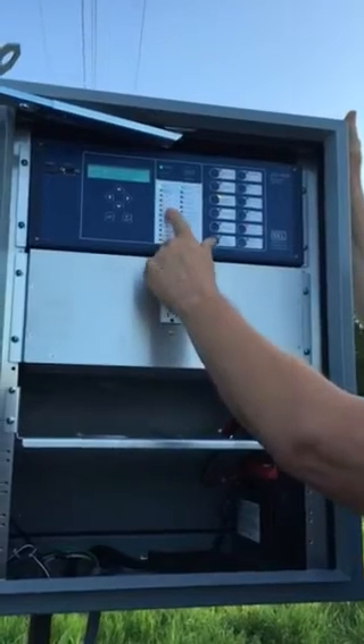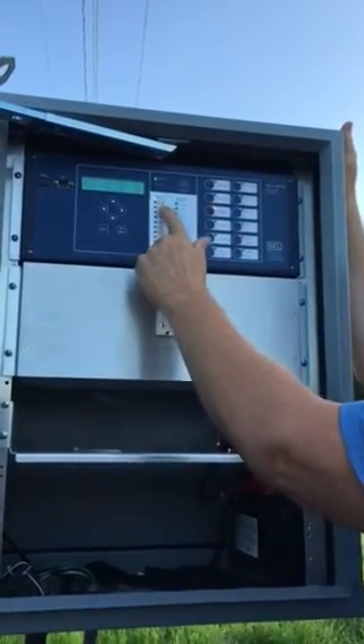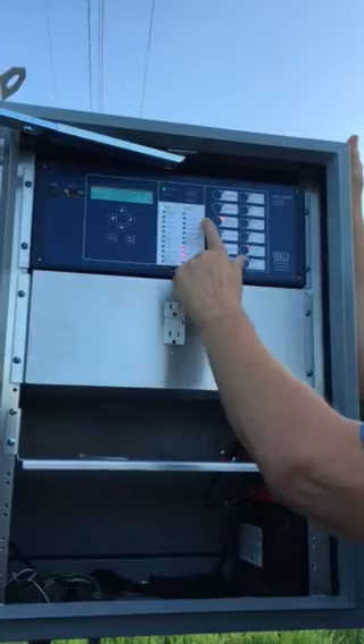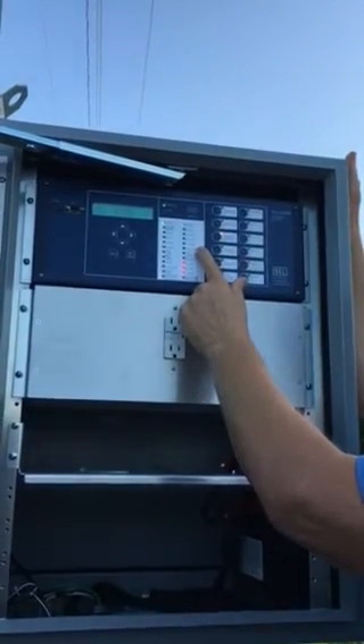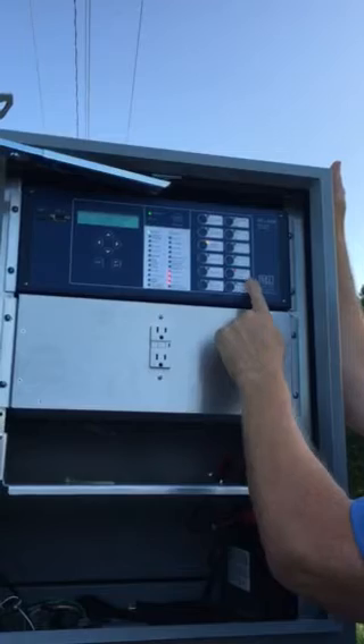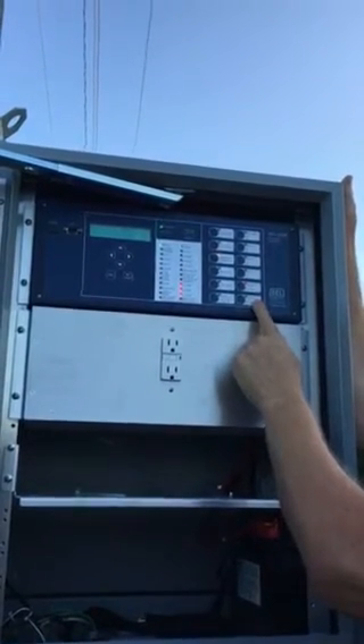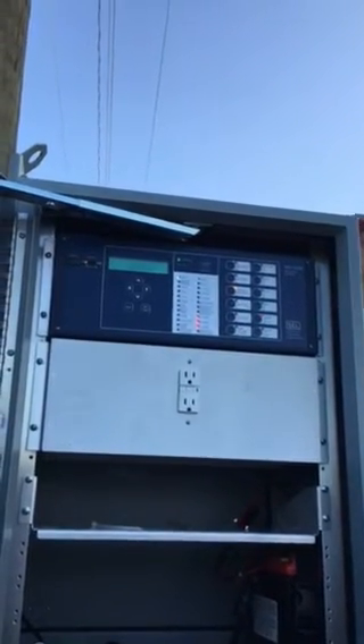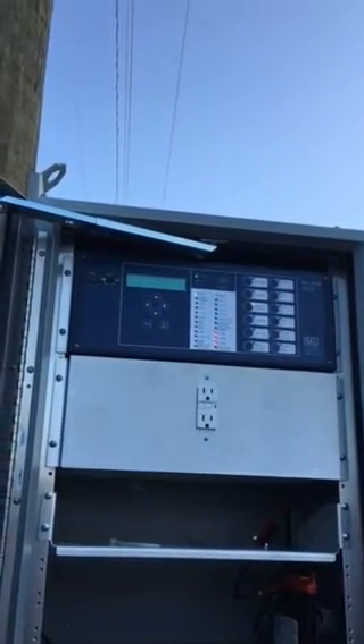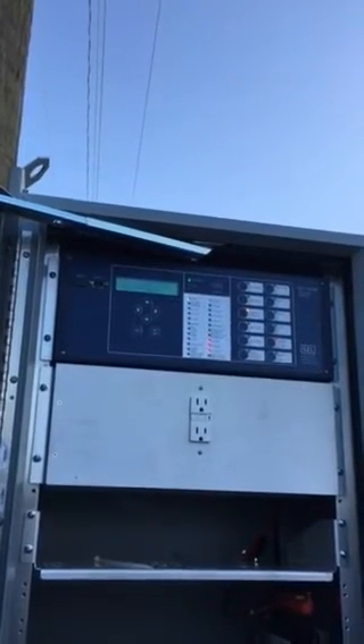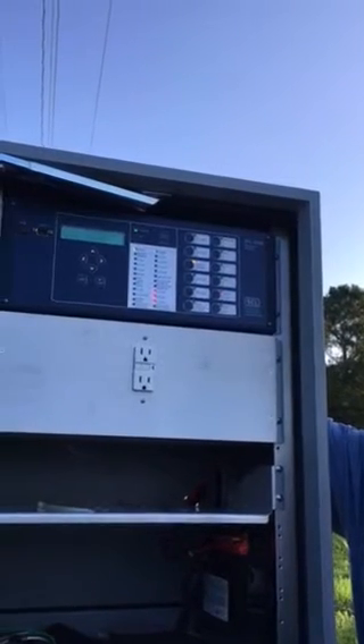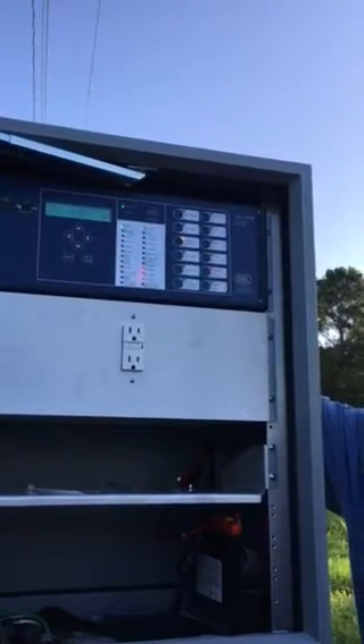If it sees a fault, these lights right here are going to light up, and all three lockout lights will come on. The breaker will open. These will go off. These two lights right here will change, and that's in the open position. You got an open indicator on the bottom of each one of those insulators up there. If you see the red rings around it, it's open; when it's closed, there's green rings around it. So it's set up that all three open at the same time, and all three close at the same time. There'll never be one single operator or the other.